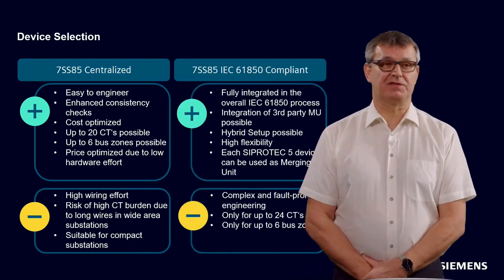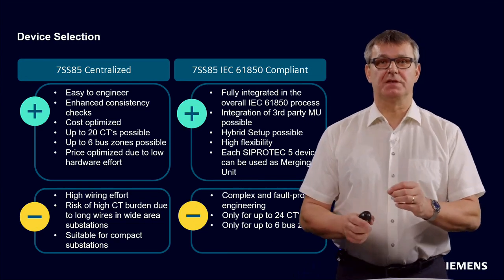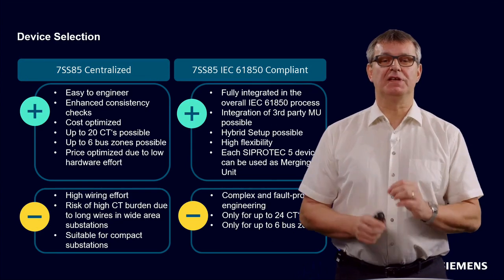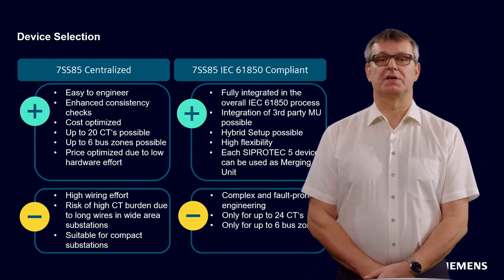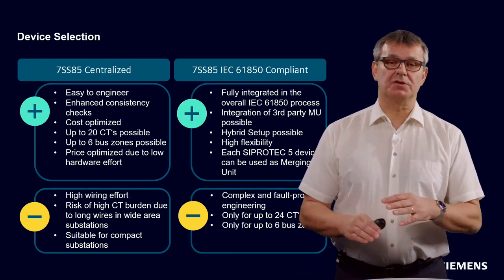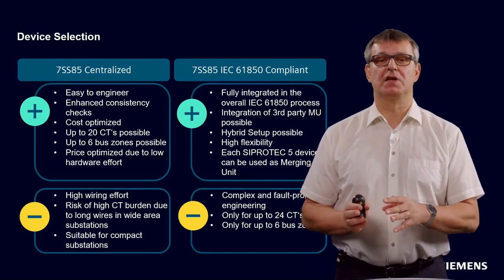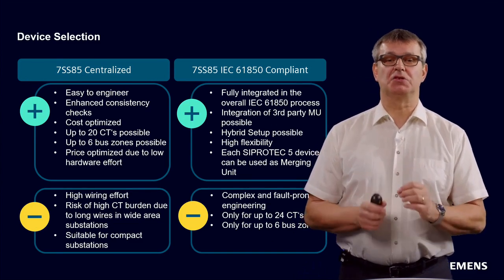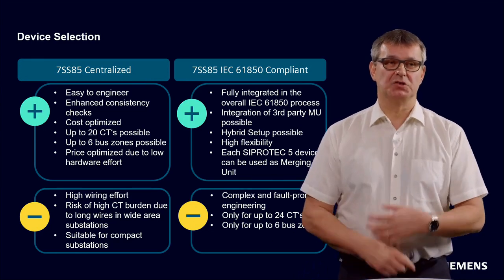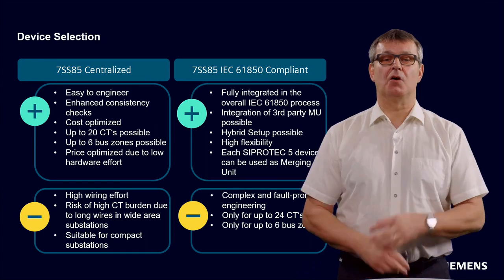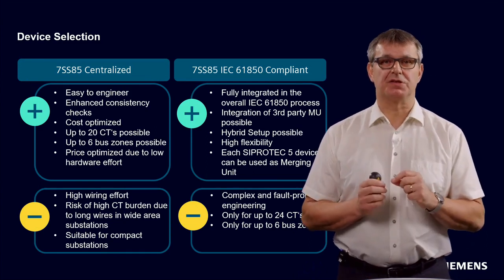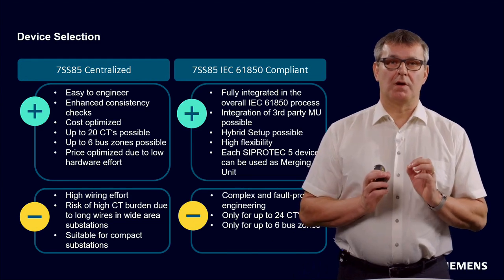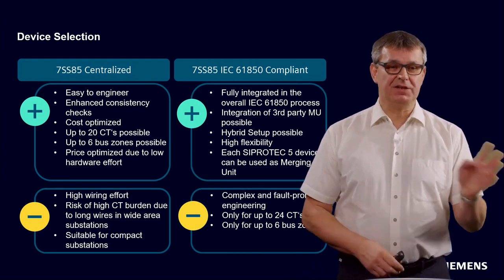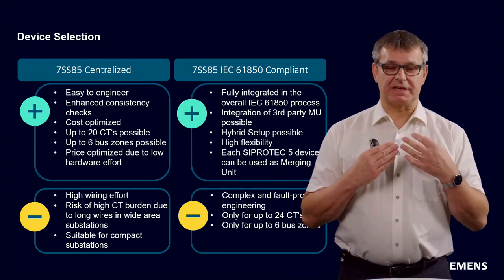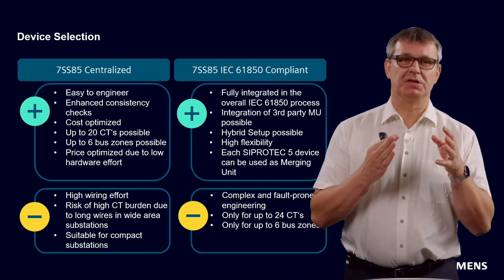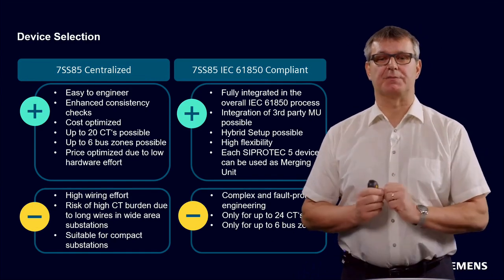The IEC 61850 compliant solution. Advantages: fully integrated. It can be fully integrated in the overall IEC 61850 process. A big advantage, also in contrast to the 7SS85, is the integration of third-party merging units, meaning merging units from GE or ABB or anything else can also be used as a bay unit for the distributed busbar protection. We can use this hybrid setup, as Nina already has explained. Hybrid setup, once again, means a combination of both distributed approach and also a centralized approach.